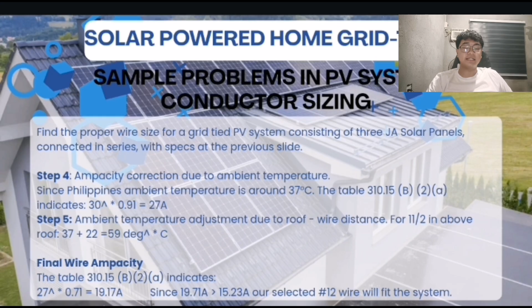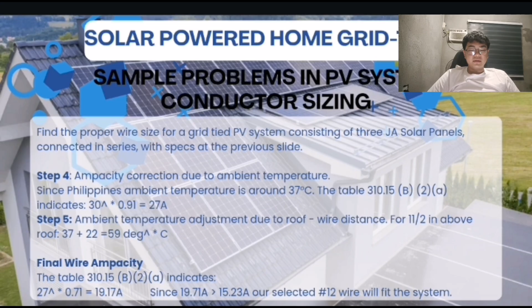So, step 5, ambient temperature adjustment due to roof wire distance. So, final wire ampacity. Sa the table 310.15 B2A indicate 27 times 0.71 is equal to 19.17 ampere. So, since 19.17 ampere is ay mas malaki sa 15.23 ampere, our selected wire is number 12. Ito ang mas magpipit sa system. So, step 6. Since there are only 2 wires inside the conduit, this step can now be bypassed.